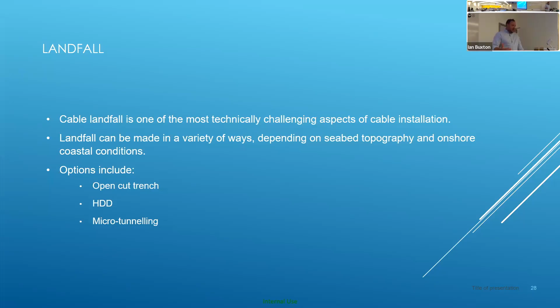Landfall open cut trench is probably the simplest solution. It's the cheapest, less risky, but only feasible when there are no environmental or physical restrictions such as seawalls. As you can see here, it's basically a sand dune, with no real limiting factors. The company that installed this cable just dug a hole through the sand dune, and can pull the cable off the cable installation vessel in the background, along the beach, and up these rollers with a big winch, probably about a 50-ton winch.